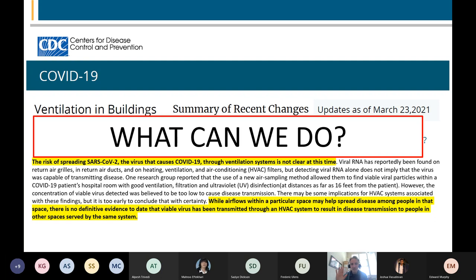And I don't have time to go into them right now, but in discussion after the presentation, I can bring up some slides that show what those mechanisms are, and we can talk about them in more detail should you want to. It is very important to understand that a MERV filter can be more efficient at extracting both larger and smaller particles than that for which it is rated. But it's important to understand as well, it may not be effective if the particles cannot get back to the filter. Well, it can still be efficient. It'll be efficient as rated, but it may not be effective because it can't get the particles to it to extract them from the airstream.